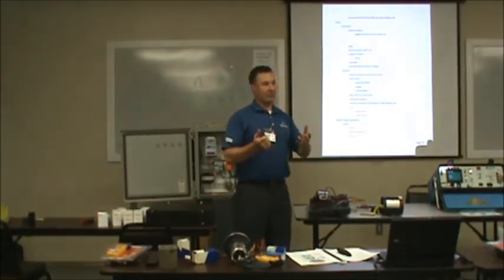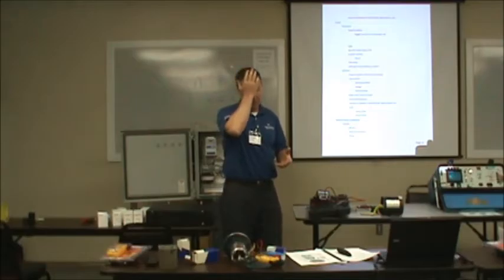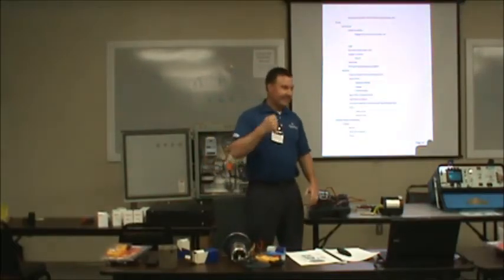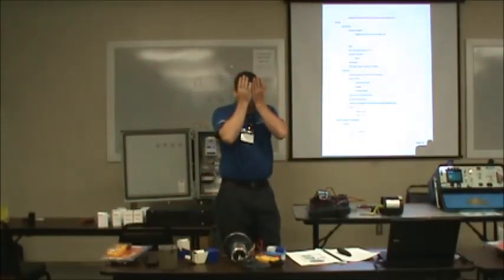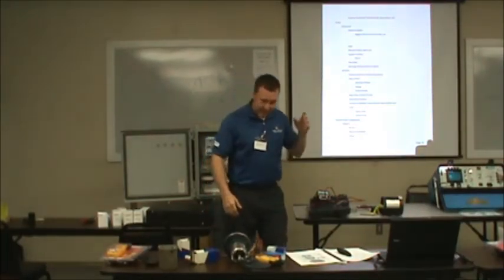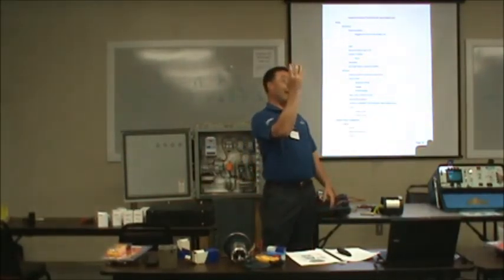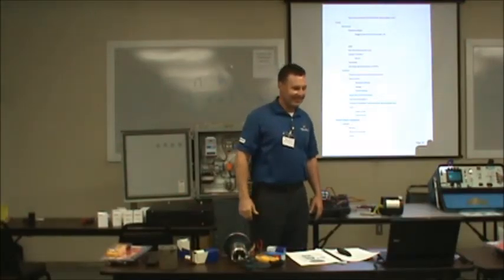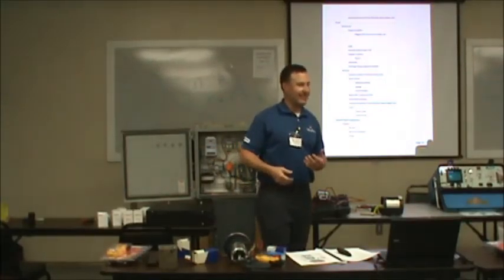They called us on Friday or Saturday. We turn this pump around in two days and have it back to them, maybe even 24 hours, I don't remember. We keep a lot of parts and stuff. Two days later, they call me and say, David, this pump is burnt up. And that's my reaction: oh, here it is, I've done blown it again. I get in my truck, go to Bowling Green, and pull the pump out of the station. Concrete block stuck in it, got the pump locked up. But they won't blame me to begin with. So I get a vac truck in there to clean the station.